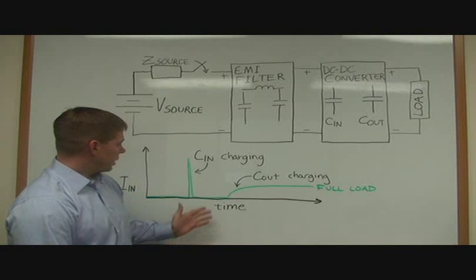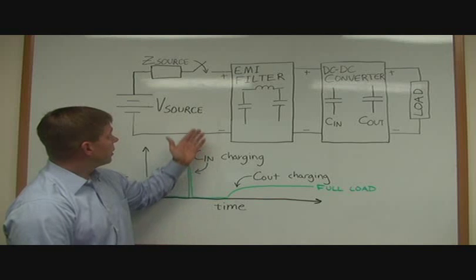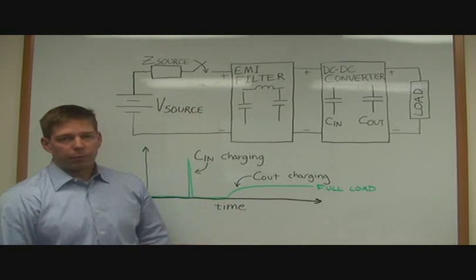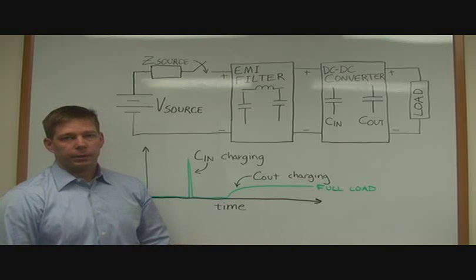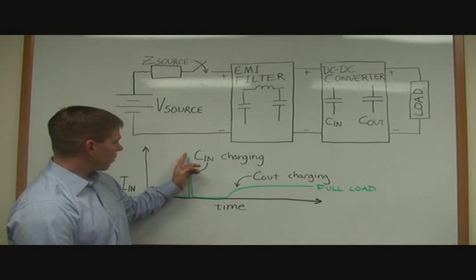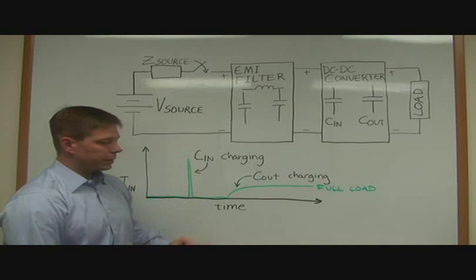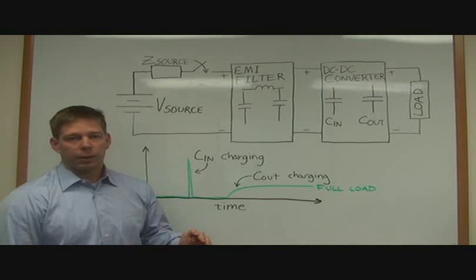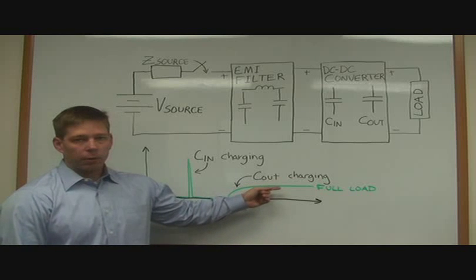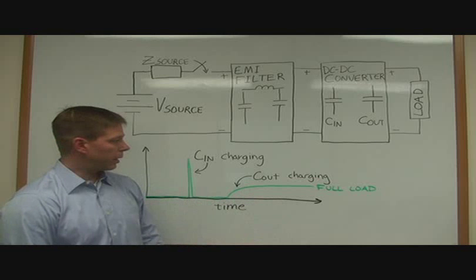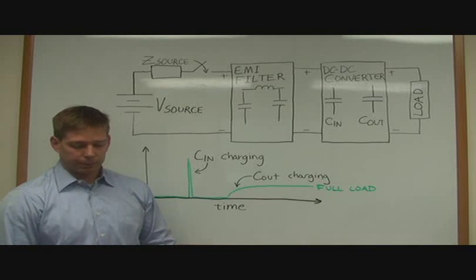So in those cases, the fast DVDT of the input voltage and the low source impedance causes this current to rise very rapidly, can reach peaks many times higher than the typical full load running current, and that can cause EMI issues in a system.